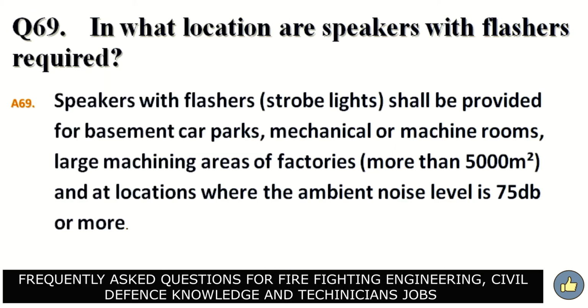In what location are speakers with flashers required? Answer. Speakers with flashes, strobe lights, shall be provided for basement car parks, mechanical or machine rooms, large machining areas of factories more than 5,000 square meters, and at locations where the ambient noise level is 75 decibels or more.